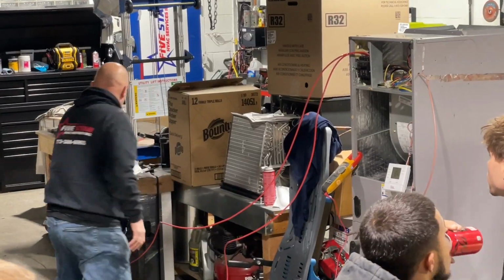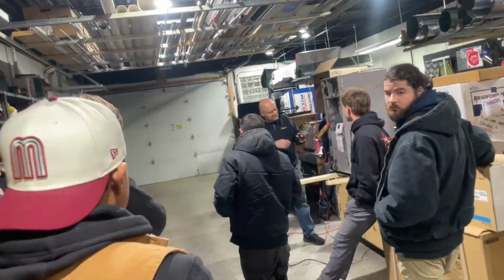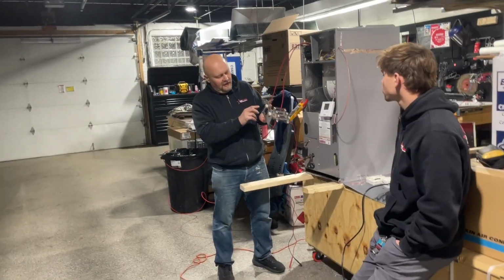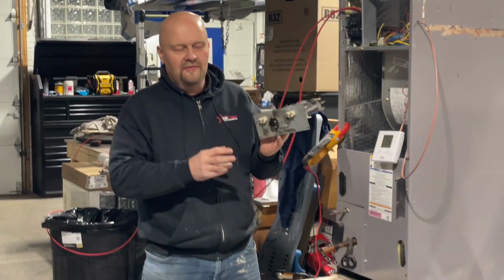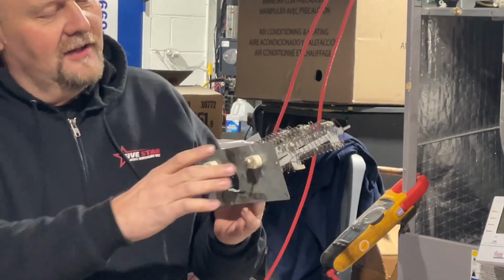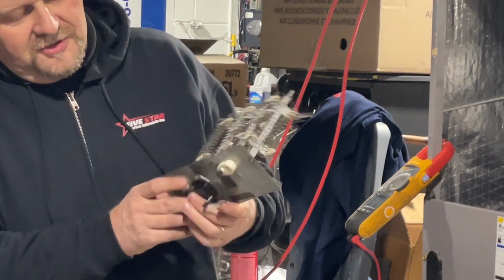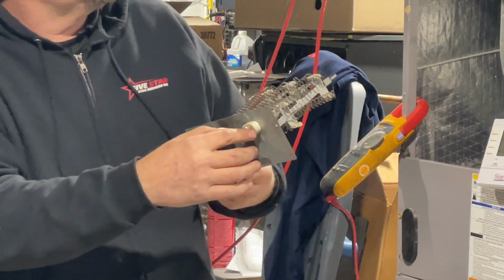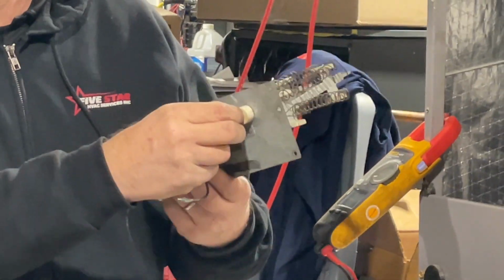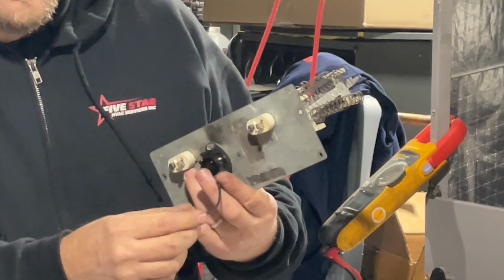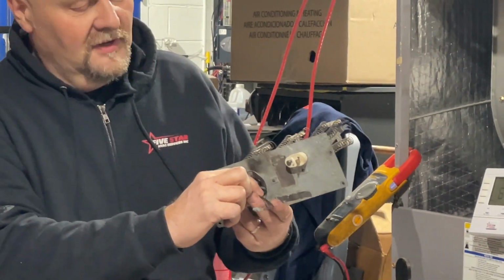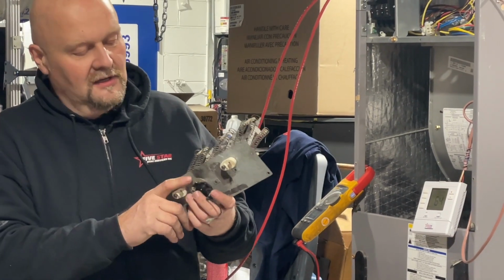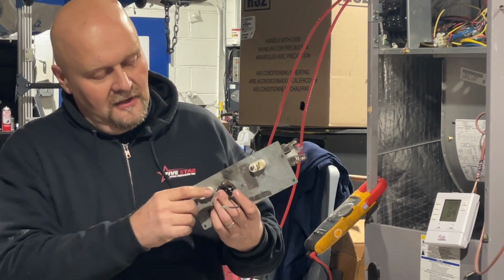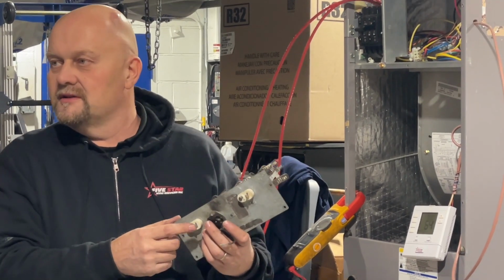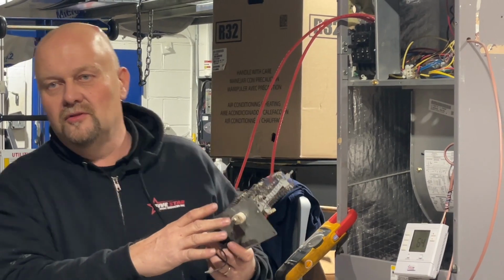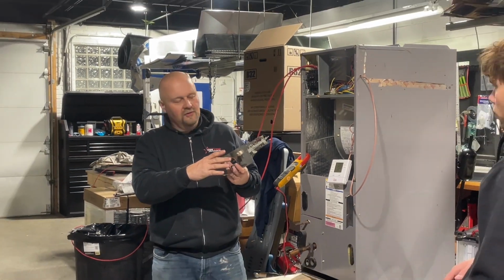Oh, there you go. So this is our electric section. Inside of this, we're going to have three of these. And all you're always going to see is where the power comes in from both sides, because it's 120 on both sides. Now the power is going to always go through a thermal disc, which is this switch. So power comes into here directly. That's one of these legs of 120 volts going to one side, right to the heating element. The other power is going to go, after it gets relayed in, to this thermal switch. If the thermal switch is cool or not overheated, this disc right here stays snapped in and power is able to flow through it and into the other side of the element. So then we complete the circuit between two phases of 120 volts to get our full 240 volt phase.